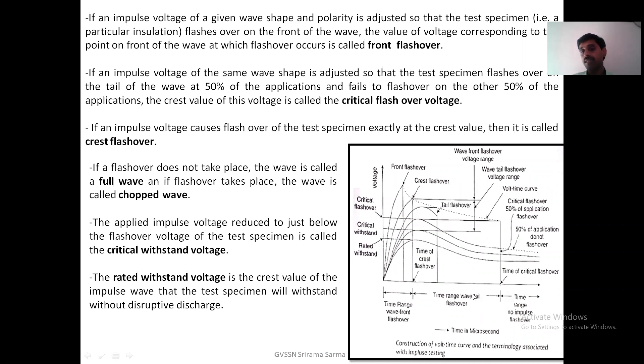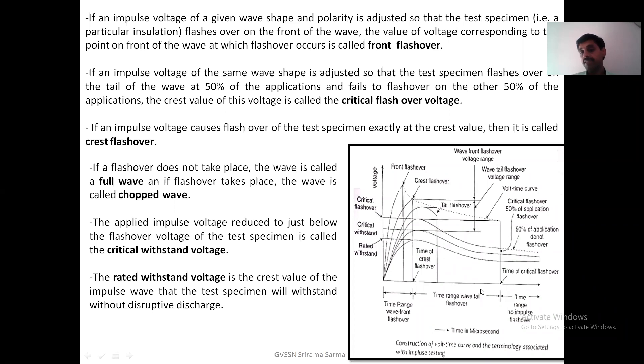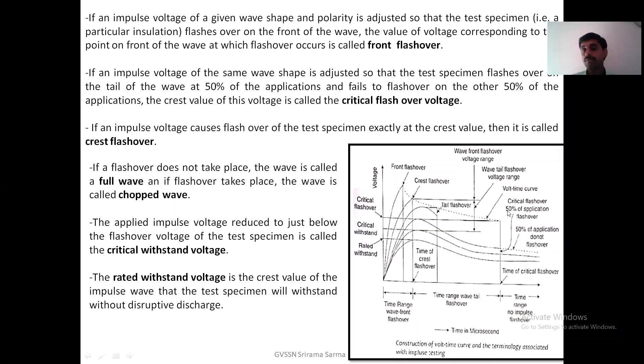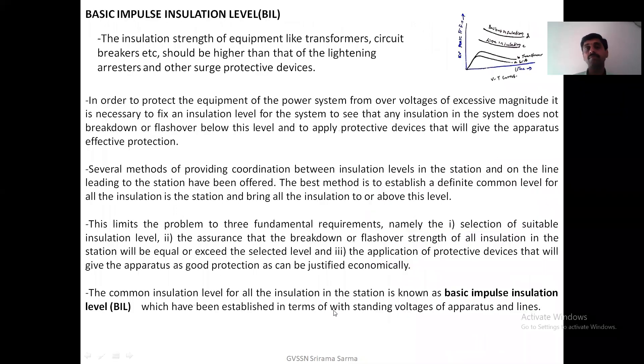From the volt-time curve, there are distinct time ranges: if the application time is in the front range, flashover occurs on the front wave itself; in the next range, flashover may occur on the tail side; in the further range, there is no flashover at all. That means the time of application is important as well as the magnitude of the voltage — both are important to test the insulation withstand level.